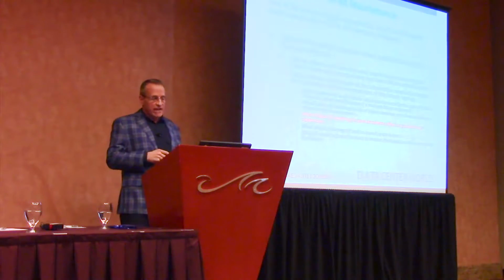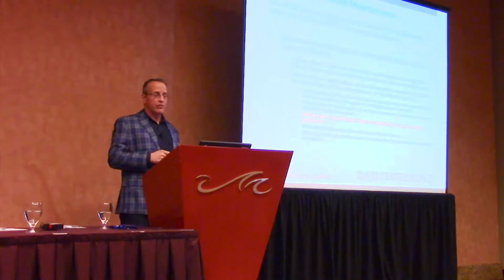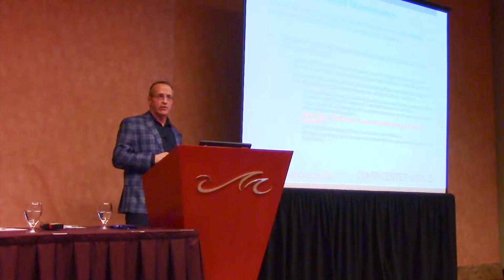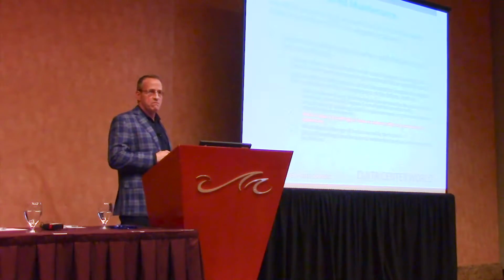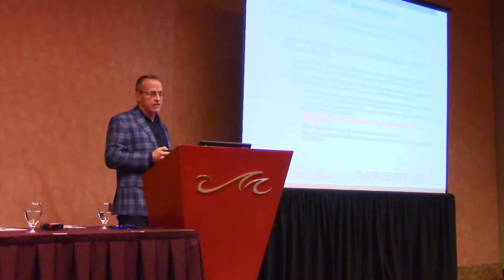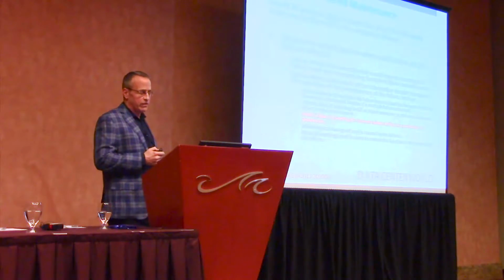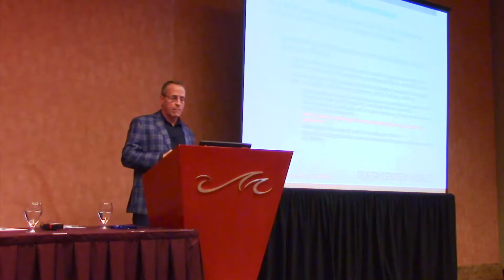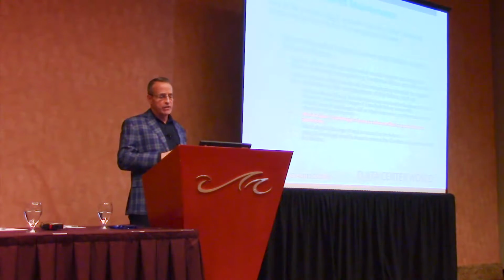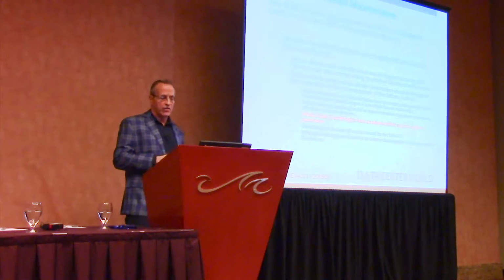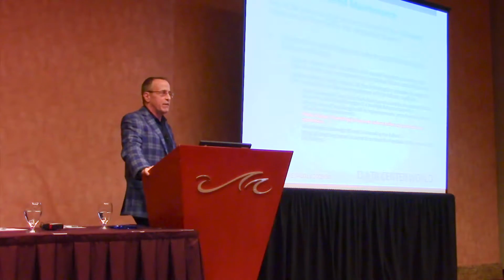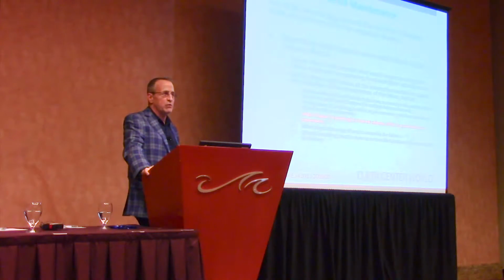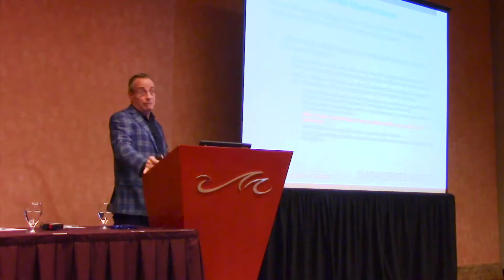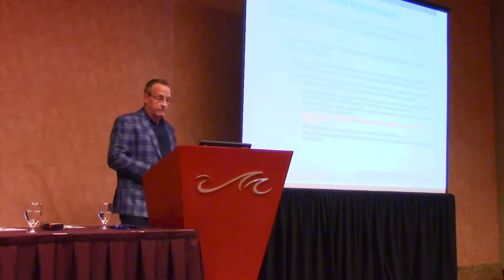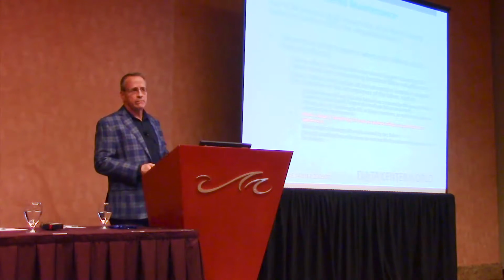Then you have to painstakingly determine what happens when each failure occurs. If this is the backup leg of a redundant system, you have a set amount of time to get it done, depending on your SLAs and uptime commitments. The real thing that mattered to us was the one I put in red: is it really going to affect production and operations? If it happens, do you even have to tell your customers that awful things happened in the background and you fixed them quickly? It's a personal, business-based decision.